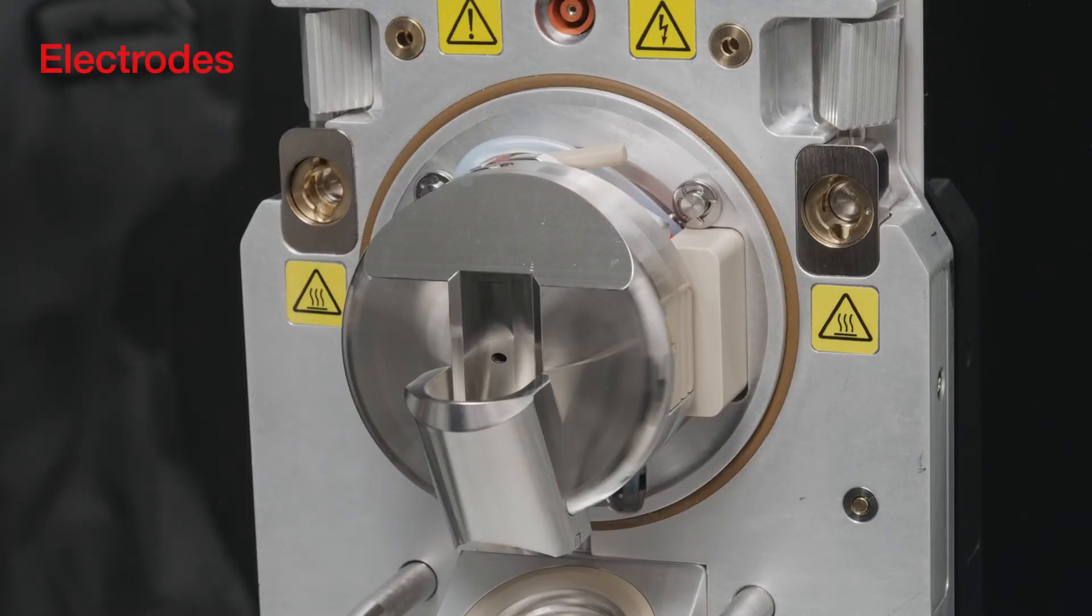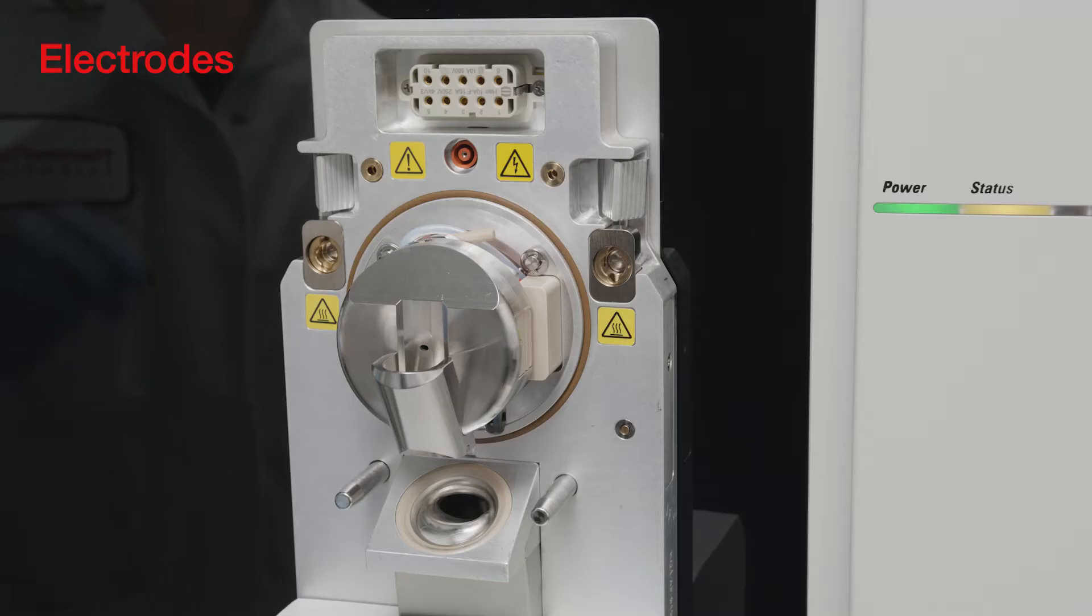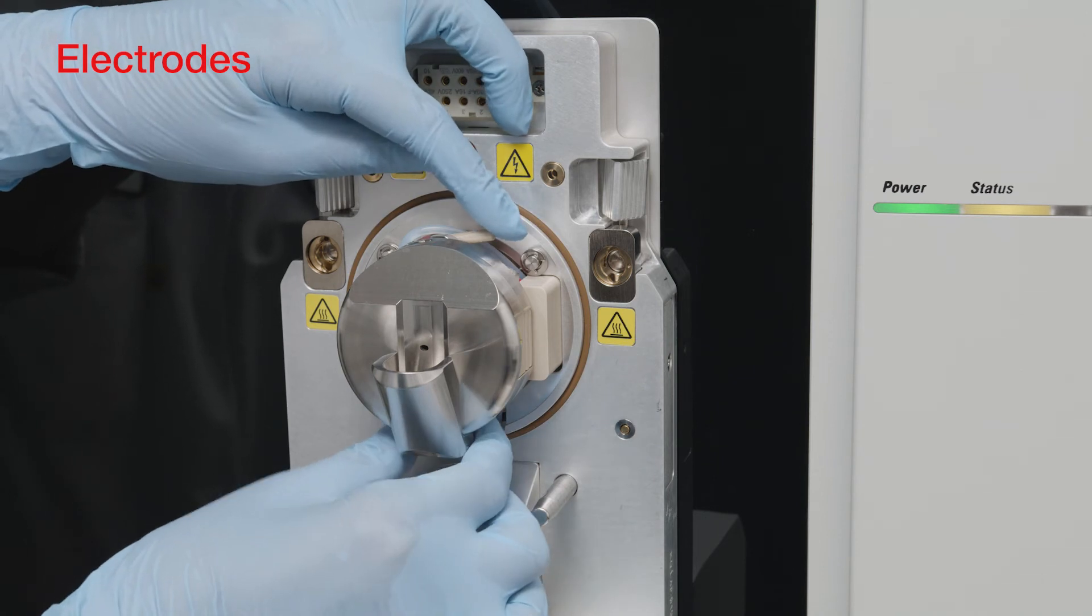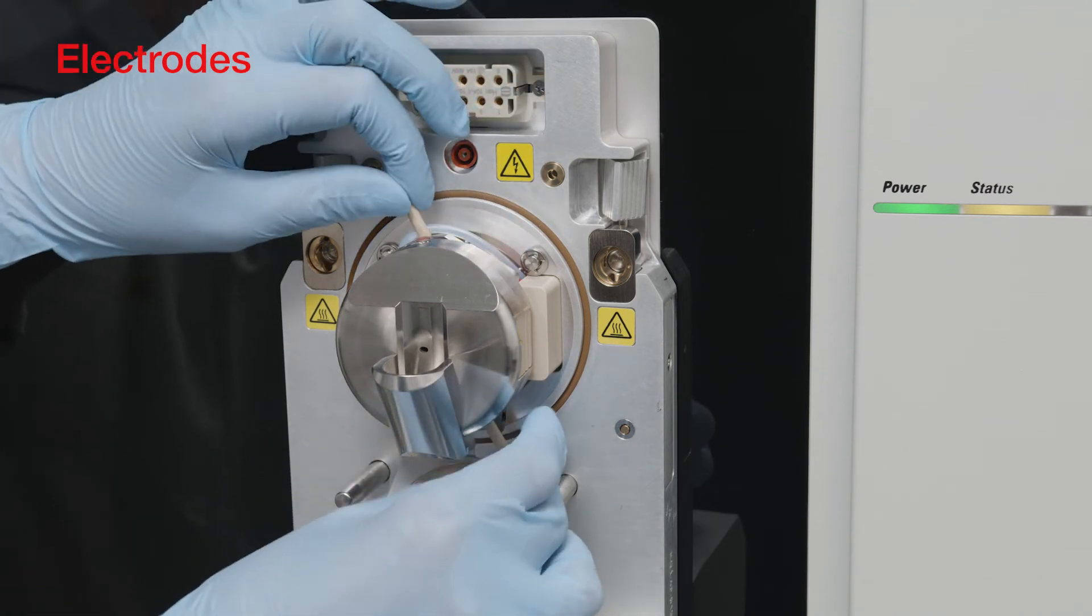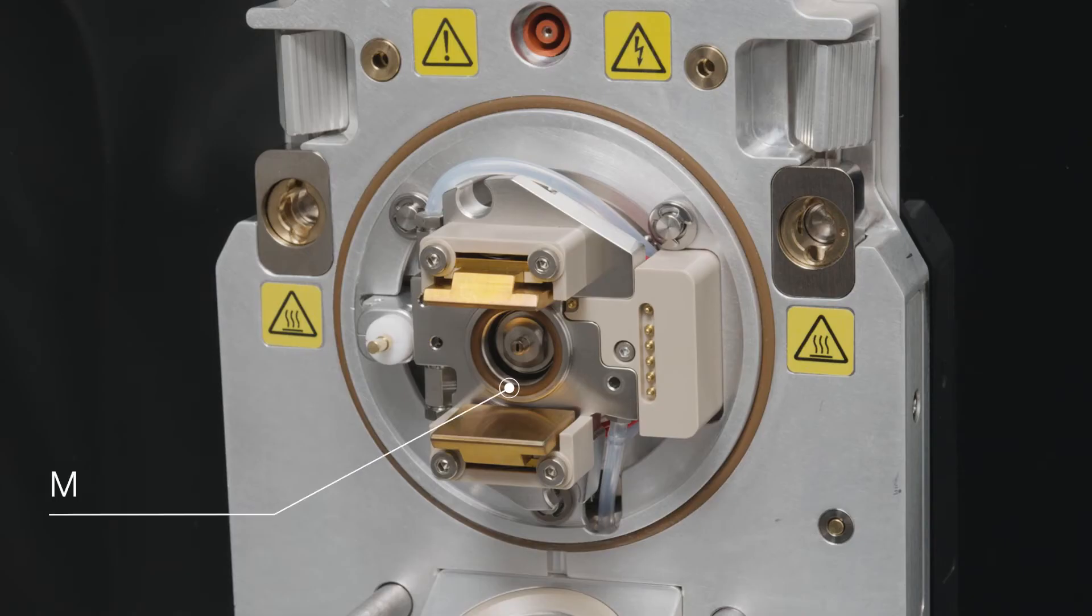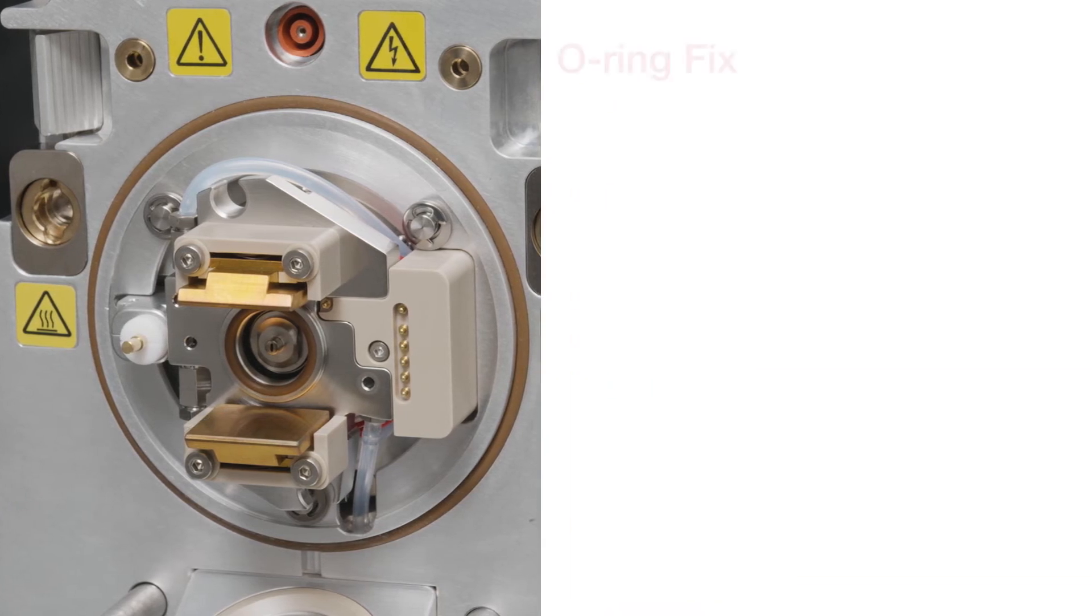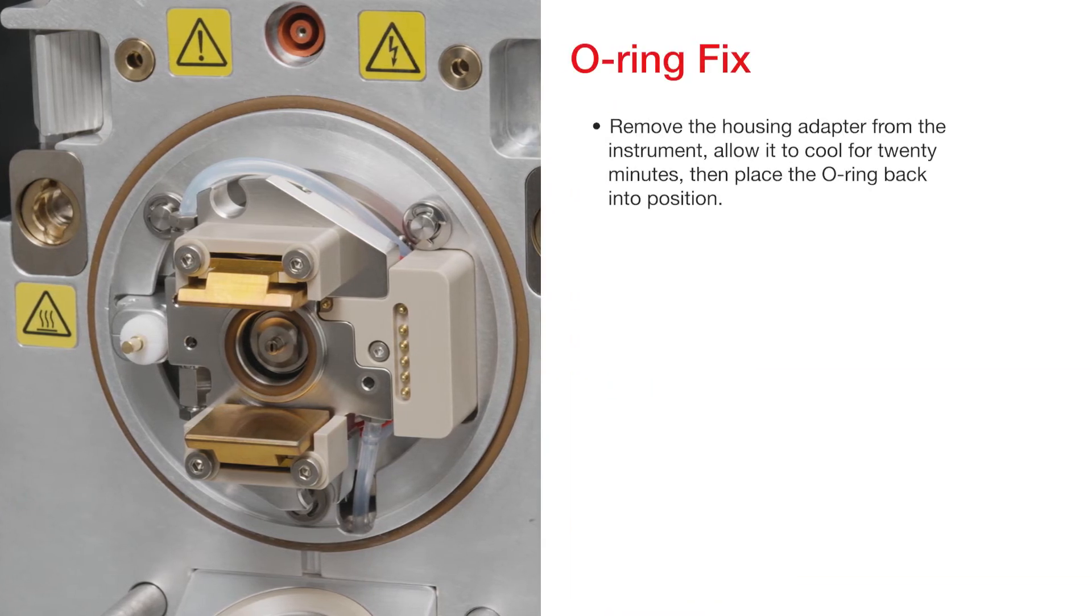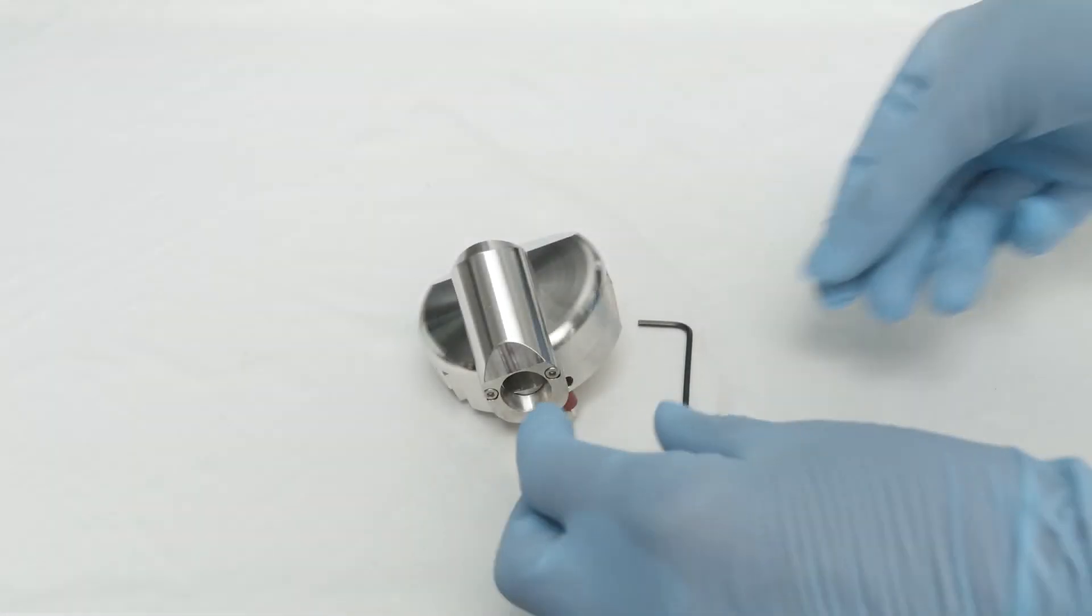Maintenance is simple. The electrode unit is designed for easy, nearly tool-free assembly and disassembly. The electrodes can be cleaned by sonication, and the only other parts that require cleaning are made of stainless steel. To disassemble and clean the electrodes, first remove the assembly from the FAIMS device and let it cool down before taking it apart. If the medium-sized O-ring should come off at this stage, remove the housing adapter from the instrument, allow it to cool for 20 minutes, and then place the O-ring back into position. Note that the O-ring is intentionally oversized to give a good seal.